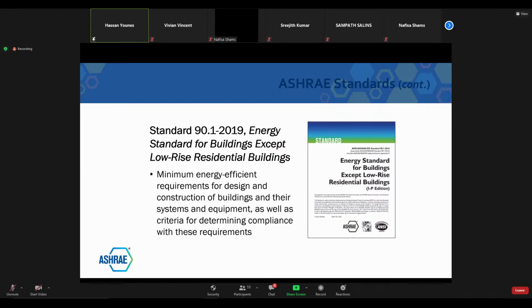Based on the weather or climate, there will be a set of requirements: the U value, the amount of insulation on the wall, the type of window, the solar heat gain coefficient, the U value of the window will differ based on that particular climate. ASHRAE does this through a kind of life cycle costing. They won't go with crazy numbers that aren't technically attainable or feasible, so they look at the market and come up with these decisions.